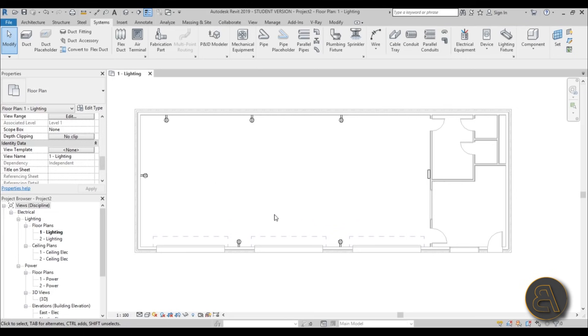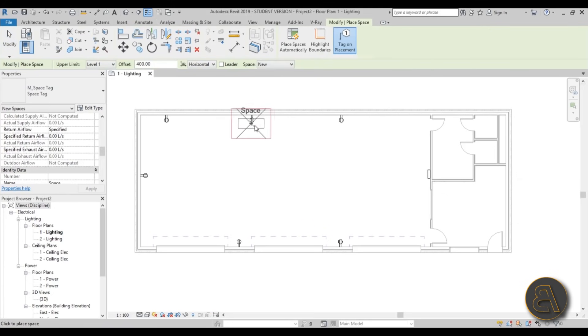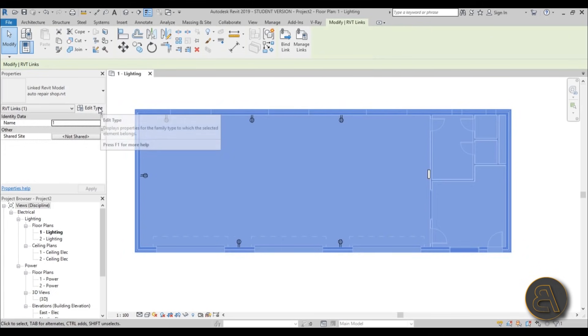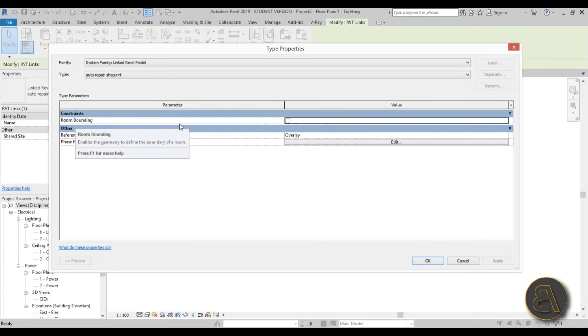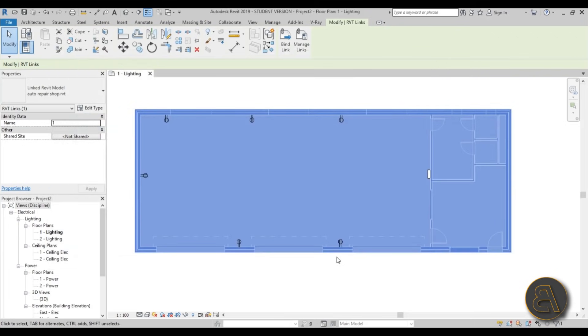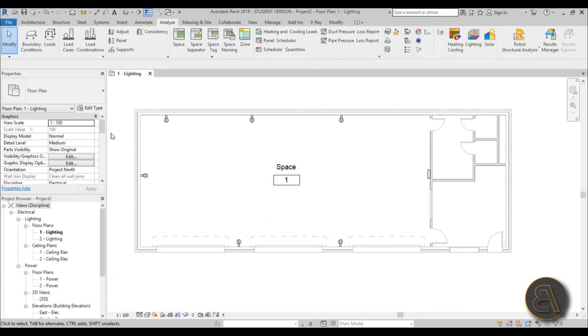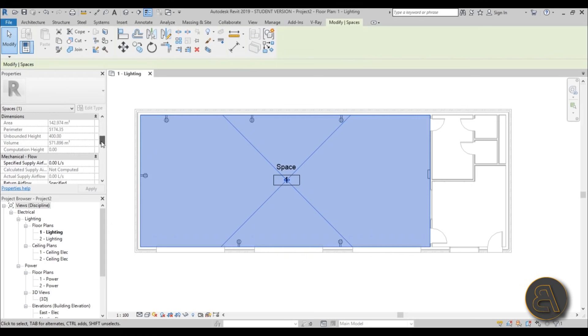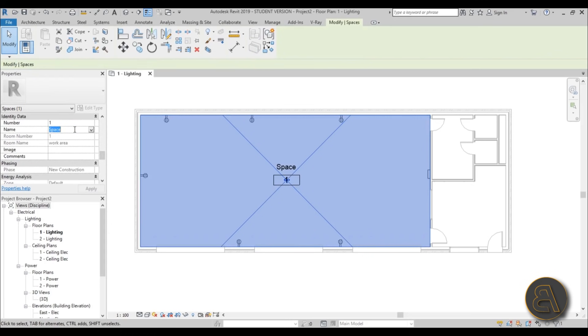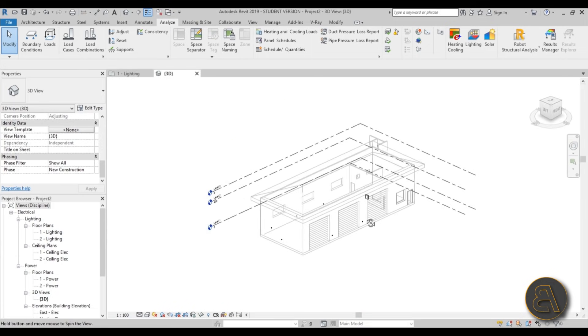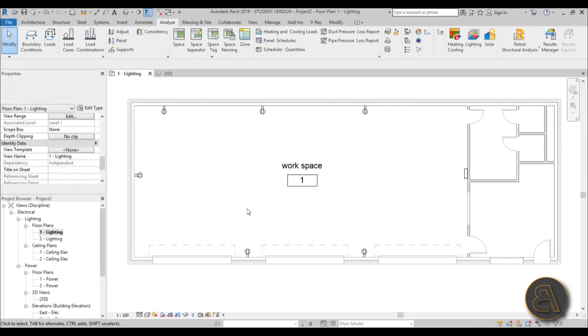Now let's create a space. Go to the Analyze tab and find the Space option. You'll notice you can't place it — it isn't recognizing the room. Hit Escape, select the linked architecture file, go to Edit Type, and under Constraints check the Room Bounding option. Hit Apply and OK. Now if you go to Space it's recognizing the room. Let's select that space and rename it — I'll call it Workspace — since this is the main working area of the auto repair shop where the cars come in.